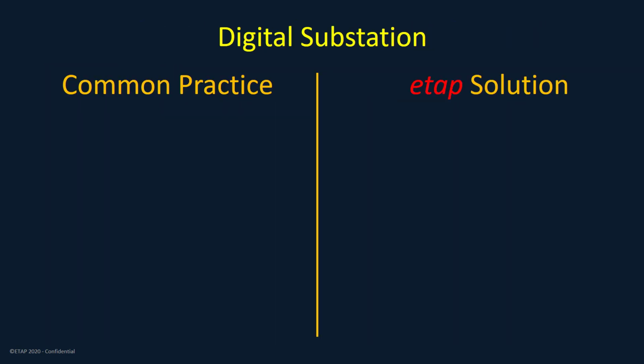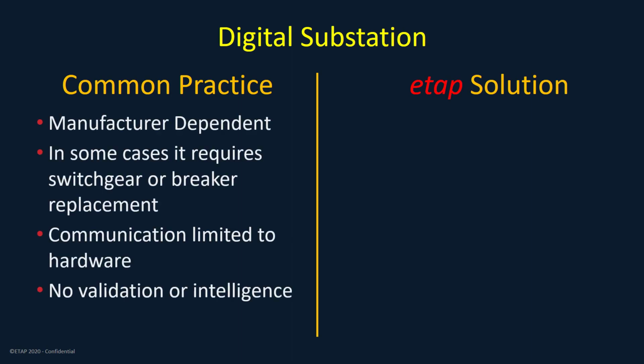Let's compare common practice against ETAP solutions. In common practice, the manufacturer of the hardware provides the entire substation. The digital substation solution is then tied to that hardware. Adding any third-party component becomes a tedious job. In some cases, when taking an existing substation, the manufacturer may require you to replace all IEDs so communication can be done appropriately. In addition, there are no validation tools or intelligence built into it.